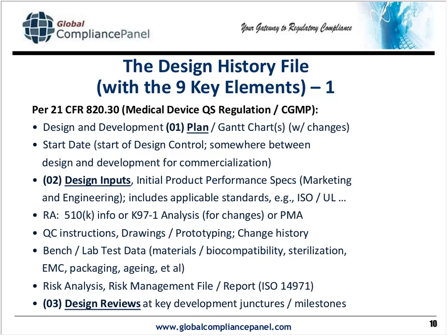More and more, this next bullet point brings out the fact that the FDA expects you to do an analysis, especially if you're changing a product. You've got a product under a 510K, Class 2 generally, under the FDA's classification system, and you're making changes to it. Well, there comes a point in time where a lot of little changes cumulatively reach a tipping point where you need to file a new 510K, and we have webinars that deal with that subject.